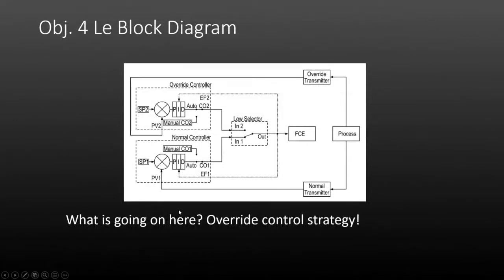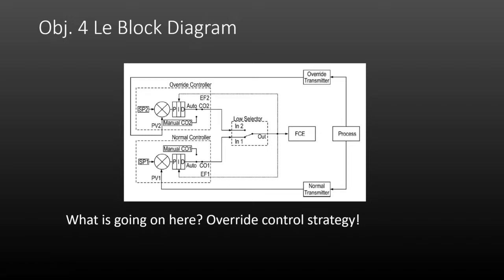Last but not least, the block diagram for selective control. Here's an override control strategy — we have a normal transmitter, an override transmitter, and a low selector simply selecting between the two different measurement signals and providing that to the output. Oddly enough, they don't show the reset tieback in this block diagram. That, my friends, is the end of the entire process section. Congratulations.